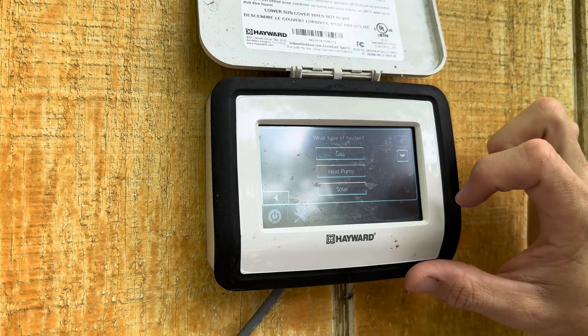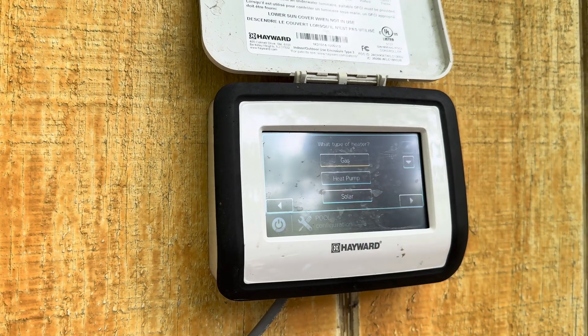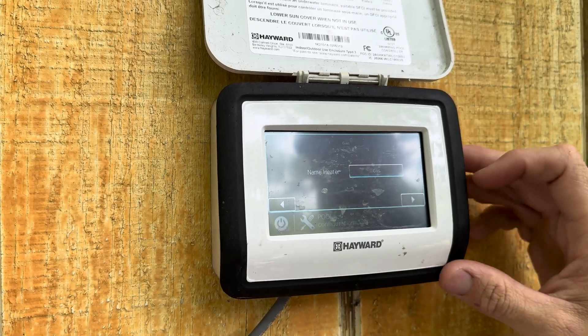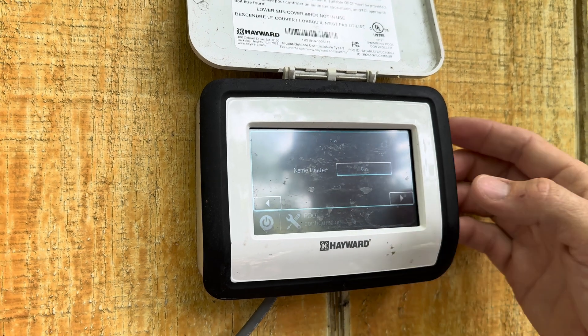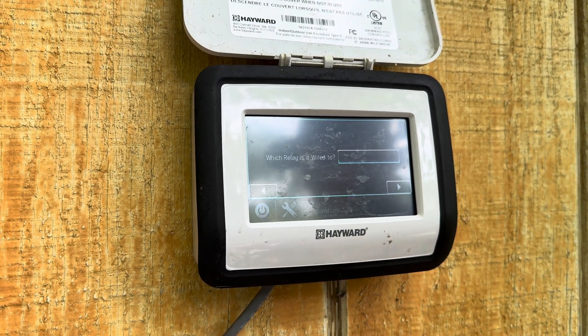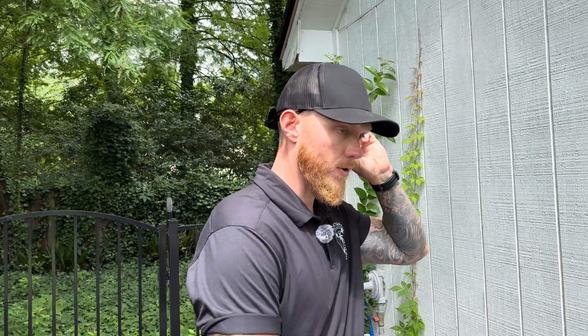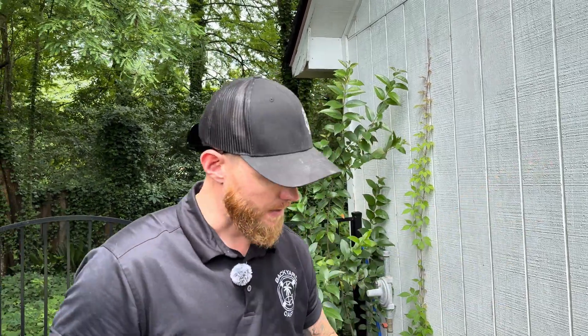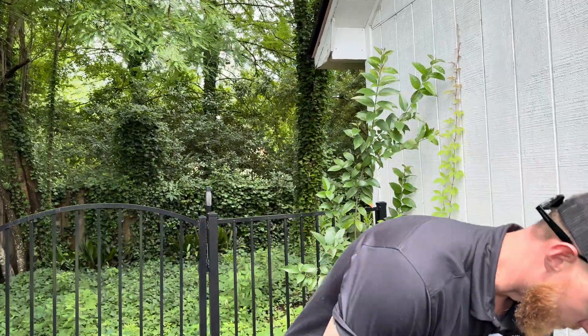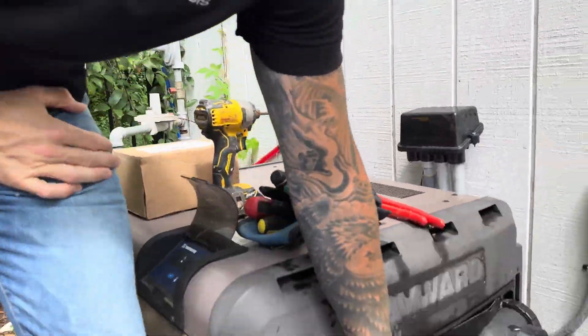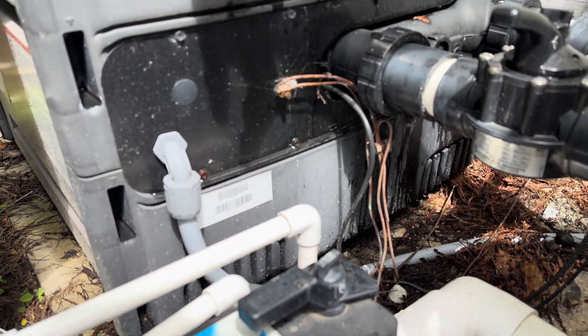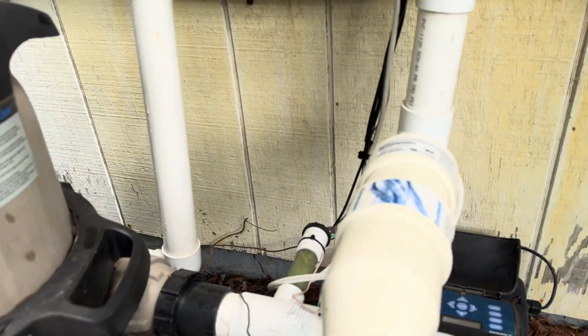This is a gas unit that runs off liquid propane. We'll just name the heater 'gas.' Now this is where we find the relay it's wired to. One thing we looked for initially when we got the call — that he can't control his heater from the unit — is to make sure there is a data cable hooked up. This heater, in order to be fully bypassed, has a data cable that hooks into the control board of the heater and into the control panel of the Omni. We haven't checked the wiring yet — we're just starting with the basics — but this data cable runs straight through the system and into the Omni panel.